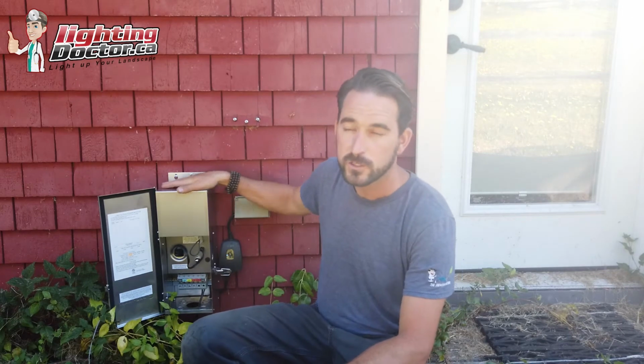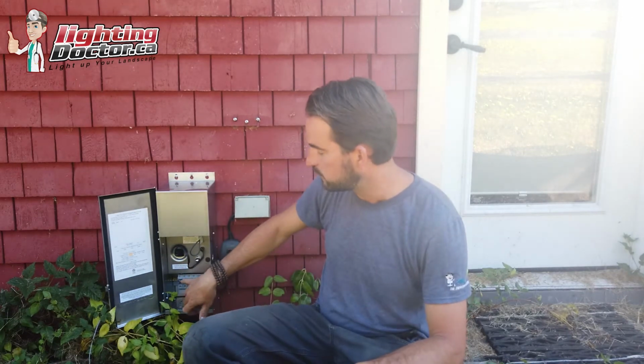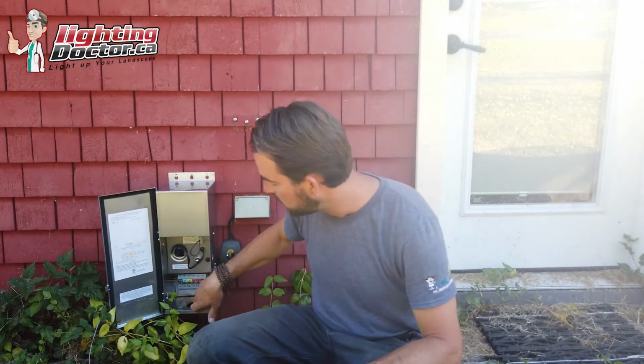On some of our smaller transformers that are 150 watts, they'll only have two terminals. They'll have your common and your 15 volt tap, and that's it. And I always get asked, can I have more than one wire running into that, because I have lights out that way and lights out that way, and I want to make two separate runs? And the answer is yes. On those transformers particularly that we carry, you can have up to 3 runs, 3 wires that will fit up into those terminals that you can run out in 3 different directions.